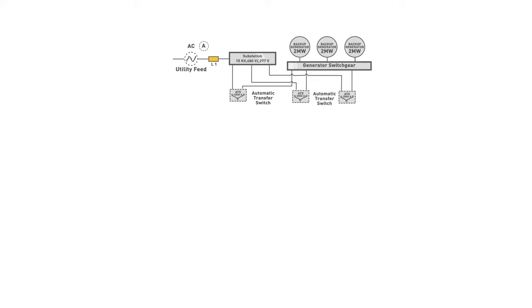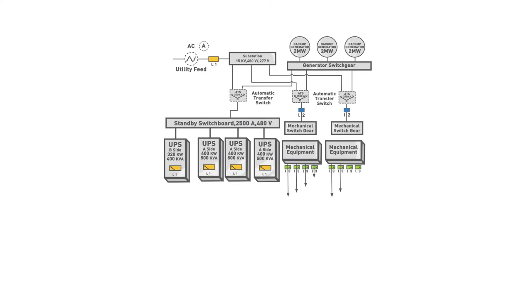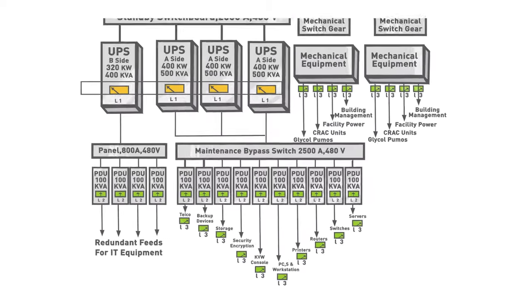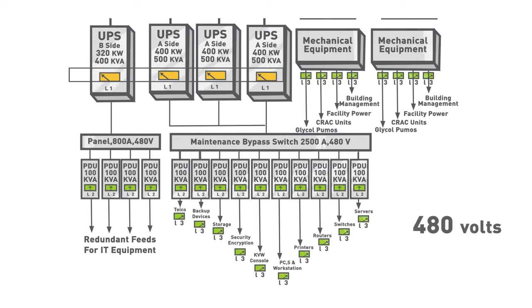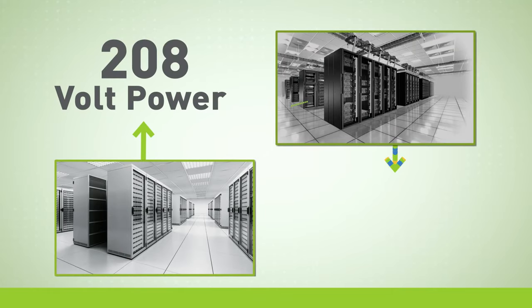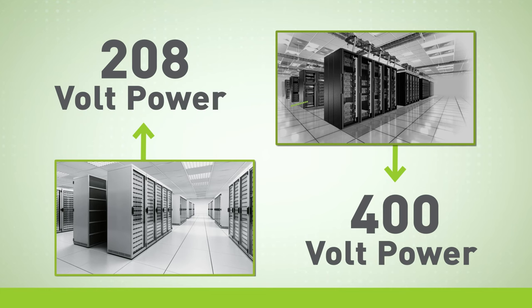The power from the UPSs is usually wired to the power distribution units, frequently referred to as PDUs. Note that these very large PDUs are not the same as the rack PDUs we'll reference later. In these videos I'll refer to these large PDUs as floor PDUs to differentiate them from the rack PDUs. The floor PDUs transform the power from 480 volts down to either 400 or 208 volts. Older data centers were built with 208 volt power, whereas most new data centers are using 400 volt power.